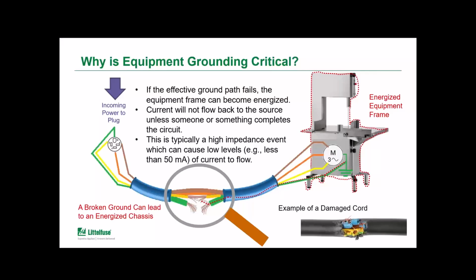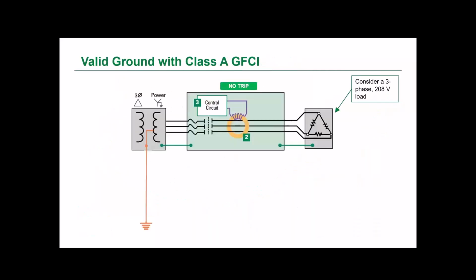And that really is why the GFCI was brought in, to be able to interrupt the circuit really quickly, even with low levels of current that are flowing. Now, unfortunately, for a GFCI to perform that job, ground fault current must be already flowing, which could mean somebody is getting a shock. So if we pose this another way, what if we could identify that shock hazard, like an energized frame, before a person was actually shocked? And that is exactly what a special purpose GFCI can do.